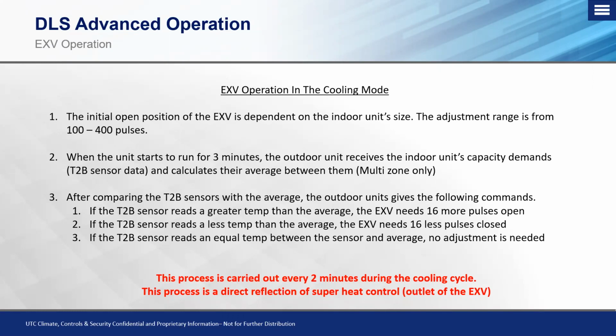Okay. If the T2B sensor reads an equal temperature between the sensor and the average, the valve doesn't make any position change. It's exactly where it needs to be. It's doing what it needs to do based on temperature. No need to adjust it. This process is carried out every 2 minutes during the cooling cycle. This process is a direct reflection of superheat control, or the outlet of the EXV, which on average, superheat, unlike traditional systems on these, is a lot lower. We usually see it anywhere from about 2 to 6 degrees superheat, but of course that ultimately depends on a bunch of different criteria.